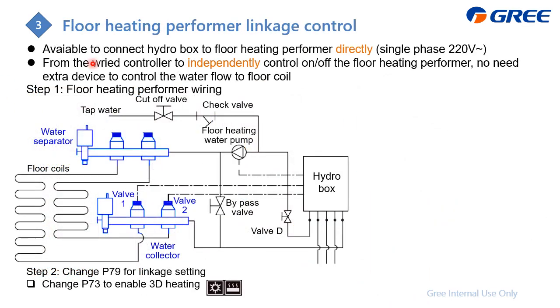Floor heating performer linkage control. The purpose of this function is just to use a wire controller to control the floor coil directly. With this one, there's no need for any other device to control the floor heating performer valve directly. From this diagram, you can find that here is the hydro box, and from here it will offer the hot water through this valve to the floor coil. At the floor heating performer, with different valves we control different coils. For example, this coil connects to here and goes back at this valve 2, and this coil will connect here and go back at this valve 1.